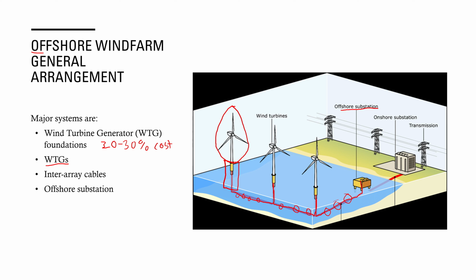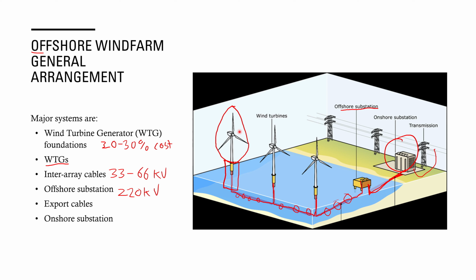So those inter-array cables will be anywhere from 33 to 66 kV. Then the offshore substation will typically transform that up to, say, 220 kV for transfer down the export cable, which goes from the offshore substation all the way along shore into the onshore substation. And from the onshore substation, it just gets connected into the normal grid. That's the general synopsis of any wind farm anywhere in the world.